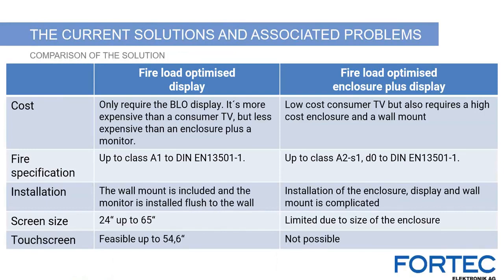Fire load optimized displays with a touch screen are available from 24 up to 55 inches. For fire load optimized enclosures, it is not possible to integrate a touch screen. The reason is the construction: the monitor itself has glass in front of the display, and in addition there is the glass of the fire load optimized enclosure with a distance between the two glass layers. This combination makes it impossible to integrate a PCAP touch screen.